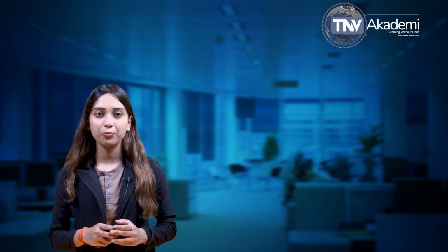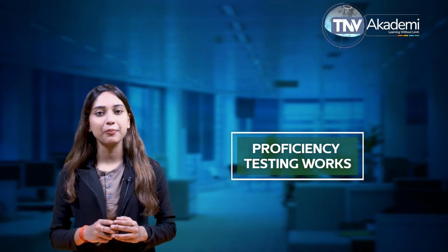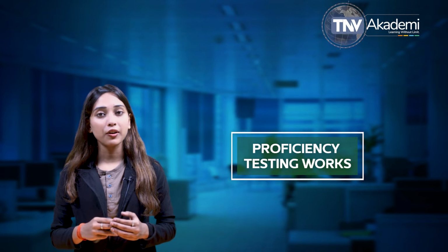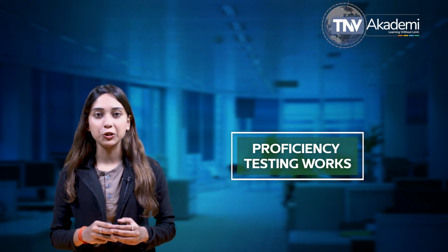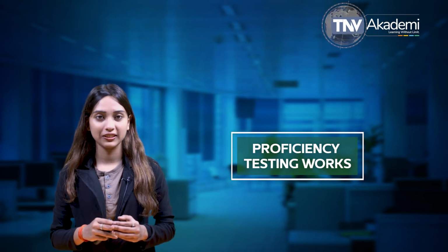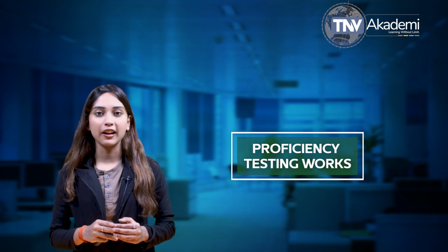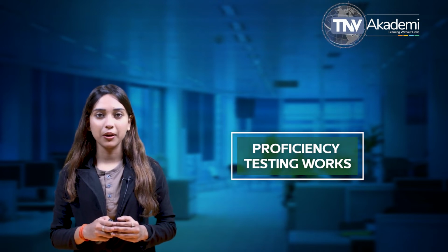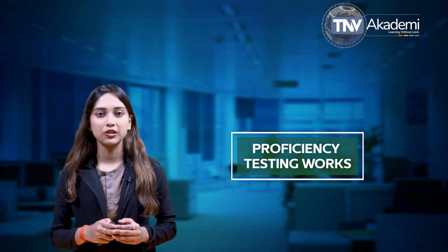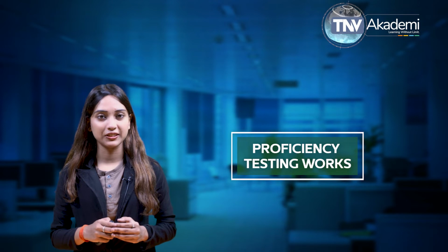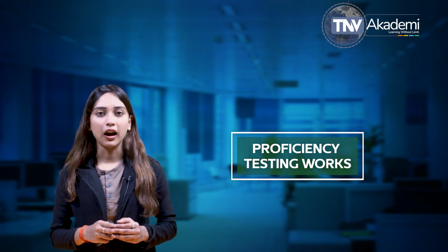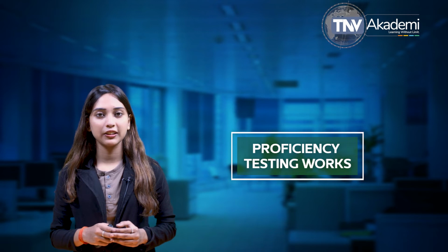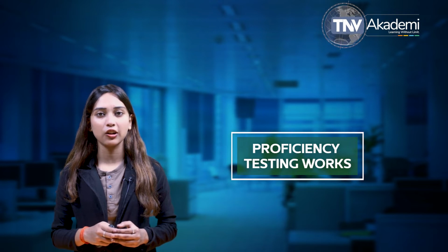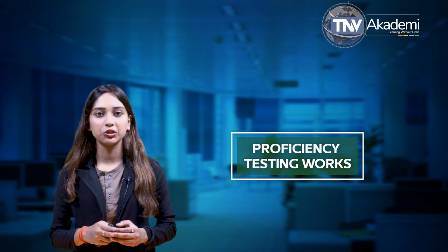Let us now discuss how proficiency testing works. Proficiency testing determines the performance of individual laboratories for specific tests or measurements and is used to monitor laboratories' continuing performance. Proficiency testing is also called interlaboratory comparison. As this term implies, proficiency testing comprises comparing the measuring results obtained by different laboratories. In a proficiency test, one or more artifacts are sent around between a number of participating laboratories. Each laboratory measures the artifacts, for example ring gauges or a set of gauge blocks, according to a given set of instructions and reports its result to the administrator.